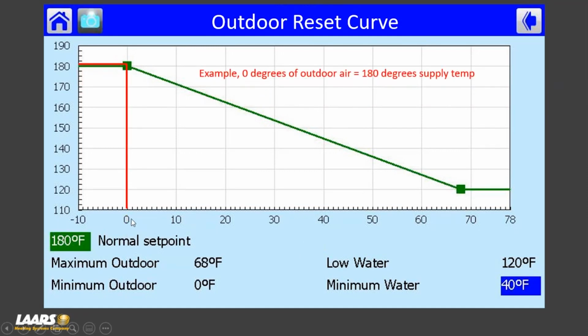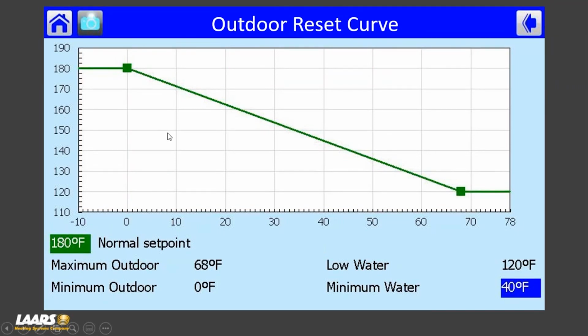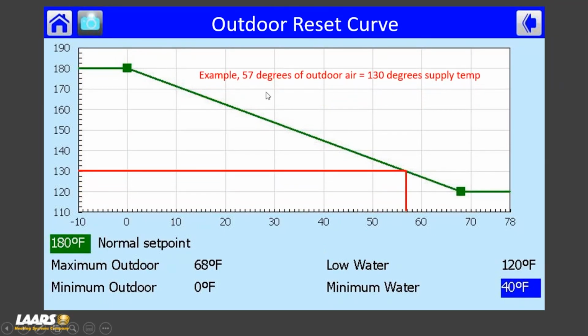So in my example, at 0 degrees of outdoor air, we'll deliver 180. However, as it starts to warm up, in this example I'm choosing 57 degrees. At 57 degrees, if we come up and plot this chart, I'll deliver 130. Based on a 20-degree delta T, that means I'm returning at 110. If I've got a 30-degree delta T, I'm returning at 100 degrees, and I'm well into the 90% efficient. So that's important to understand.